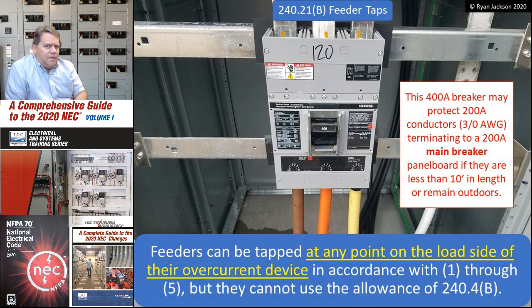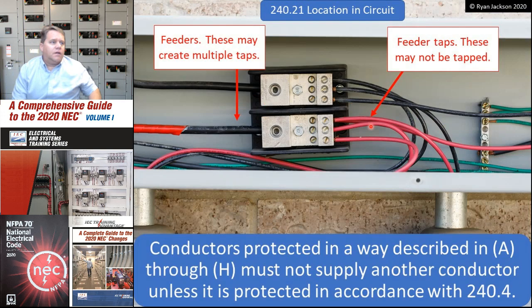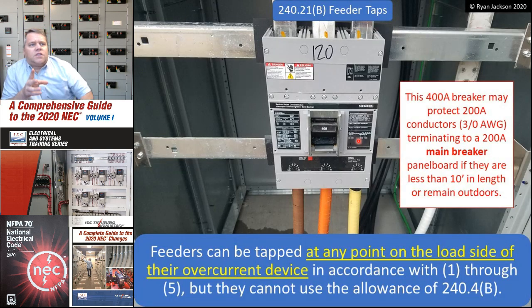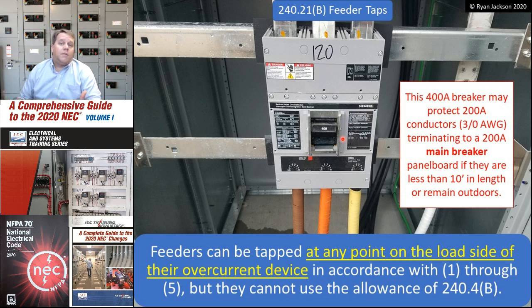The clarification that they made in the 2020, when we think of tap conductors, I think most of us think of this. You've got a feeder conductor, and it creates multiple small wires. And indeed, that could be a tap. But do you remember the definition? A tap conductor is simply a wire that doesn't comply with the regular overcurrent protection rules, but does comply with the tap rules. So what this section is trying to clarify is I've got a 400 amp breaker in this switchboard. Now, I didn't put it there, it's just happening, it's an existing building. I walk up and there's this beautiful 400 amp circuit breaker sitting there, nothing coming out of it, so why buy a new breaker? I'm going to go ahead and use it.